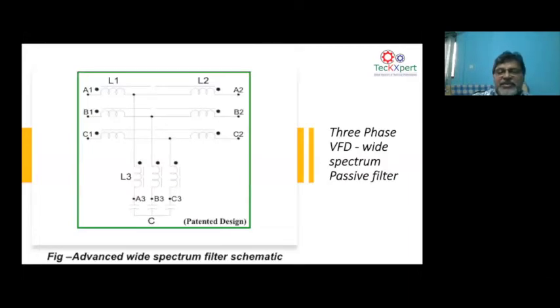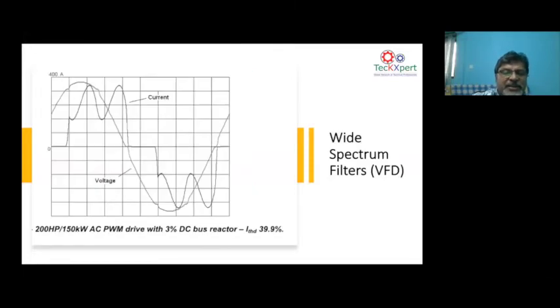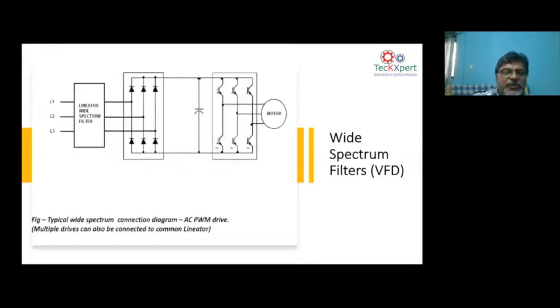This is called a passive filter. Go to the next, I can explain that a little better. When you put a passive filter at the input of the drive, here we are showing a waveform of a current which has about 39.9% harmonics at the input of the drive. Now, the passive filter is an LC filter. Go to the next slide, you can see how it looks. You put a passive filter at the input of the drive. You can see again a VFD, with input side rectifiers and output side inverters.